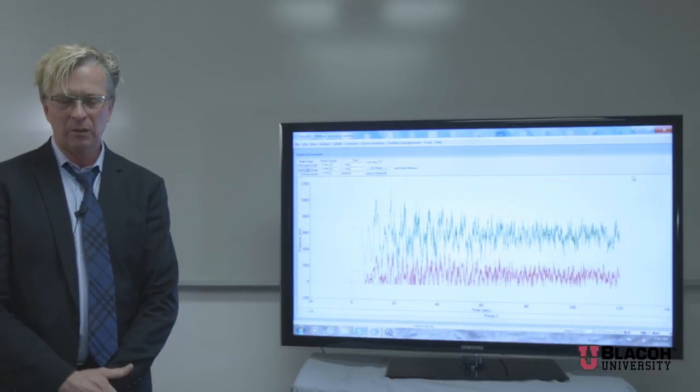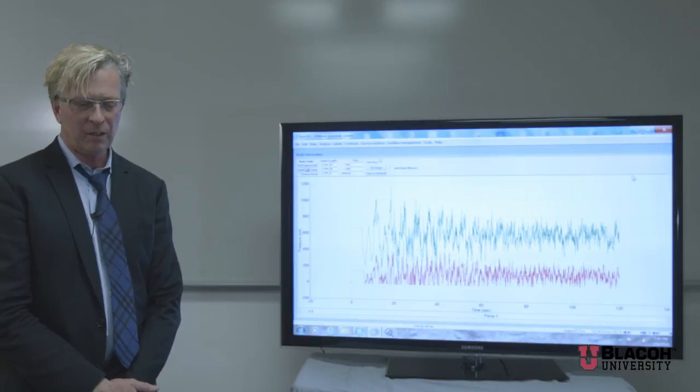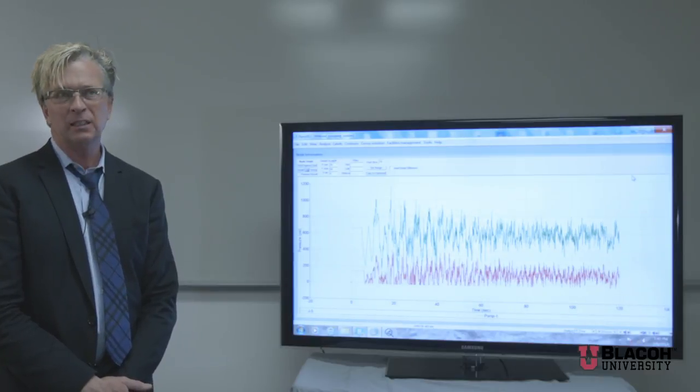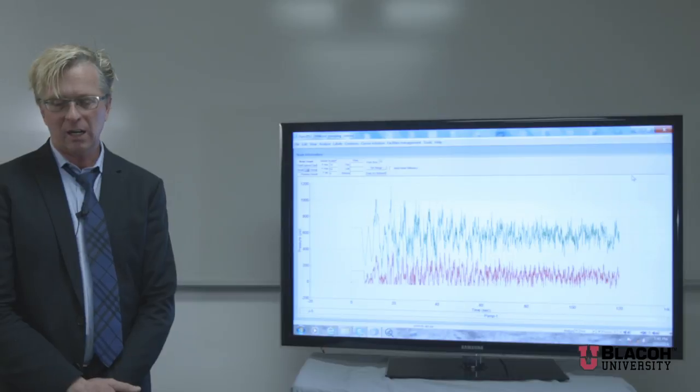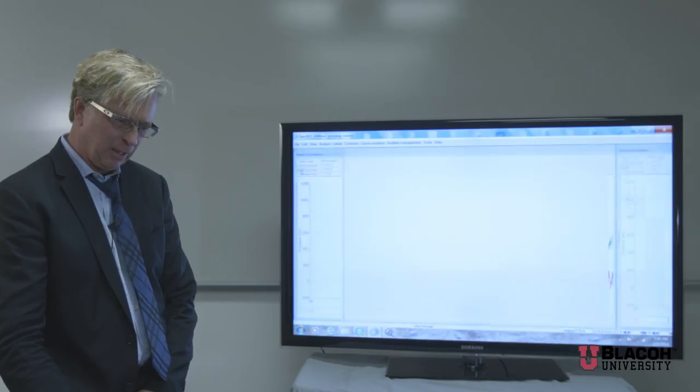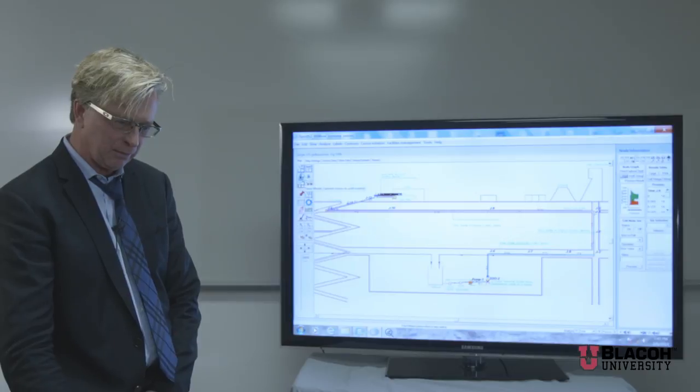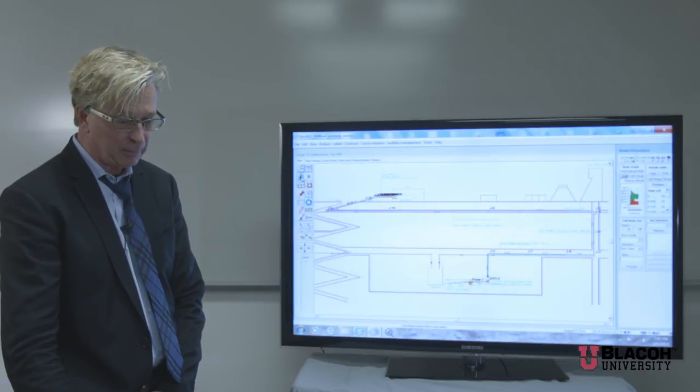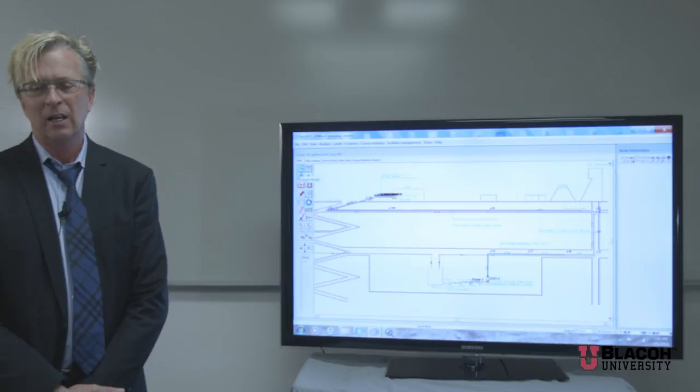This is our worst case scenario—three pumps running in series, power failure. In this application they did not have variable speed drives and they had a standard swing check valve. I mentioned variable speed drives because a lot of people look at them as ways of reducing or maybe eliminating water hammer scenarios.